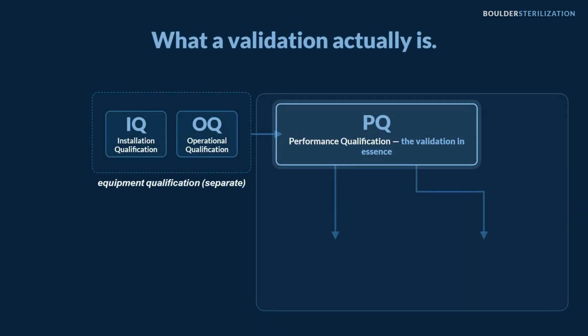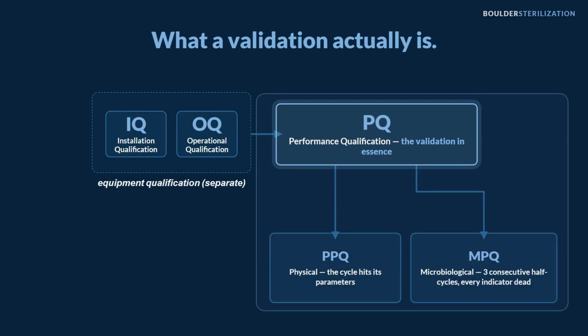And validation isn't one good run. It's built in layers. First, installation and operational qualification, IQ and OQ, confirm the equipment itself is installed right and runs right. Those are separate from the next step. Then performance qualification, PQ, and that is the validation in essence. It has 2 halves, the physical side, proving the cycle actually hits its parameters run after run, and the microbiological side, 3 consecutive half cycles, every single indicator dead. Pass the equipment checks, pass both halves of PQ, and you've shown the process is lethal and repeatable.